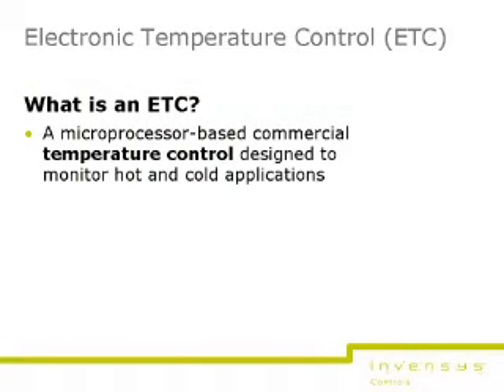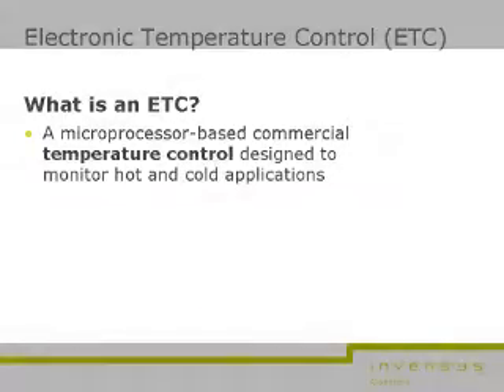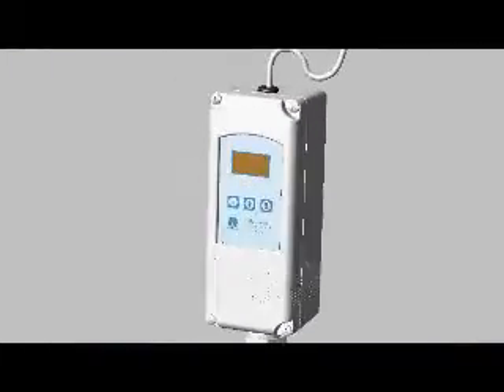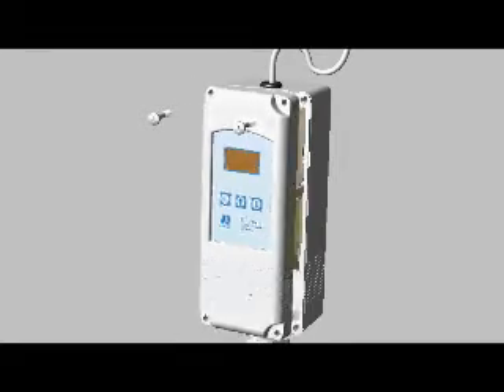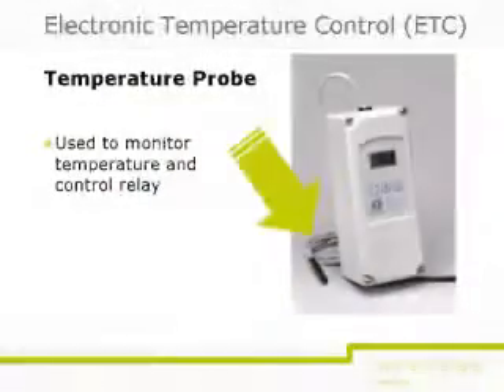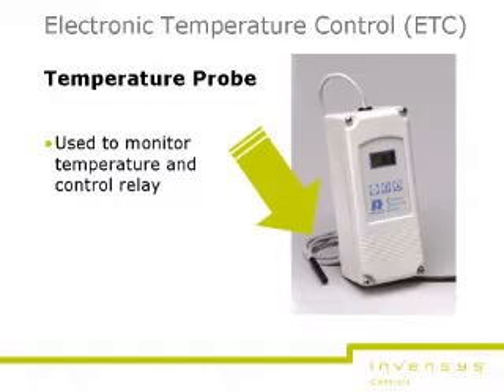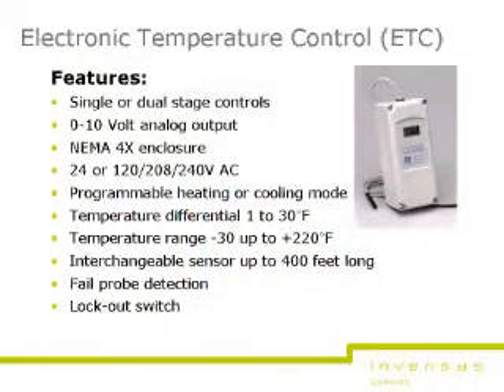What is an ETC? An ETC is a microprocessor-based commercial temperature control used to monitor hot and cold applications. It has an impressively large temperature range, spanning from -30 degrees to +220 degrees Fahrenheit, and can be used in numerous applications. This ETC is a digital control with keypad input and liquid crystal display enclosed in a plastic housing. A thermistor-based probe is used to monitor the application temperature. A microcontroller controls the logic to turn output relays on and off based on the desired temperature as entered by the user. Features include the following.